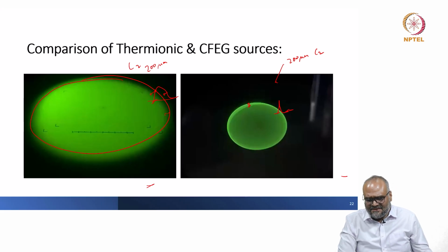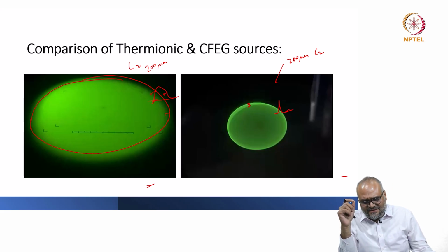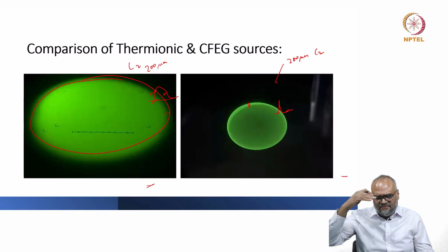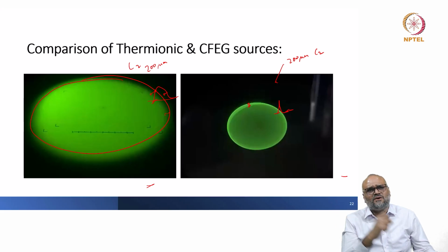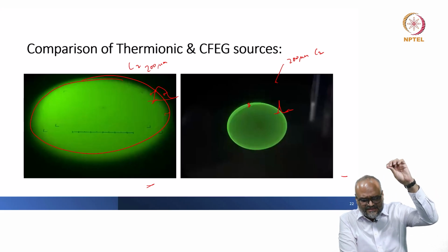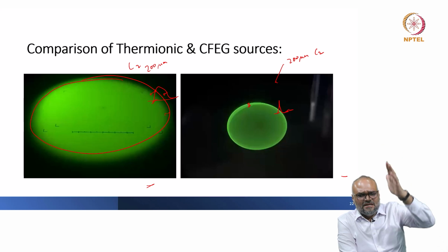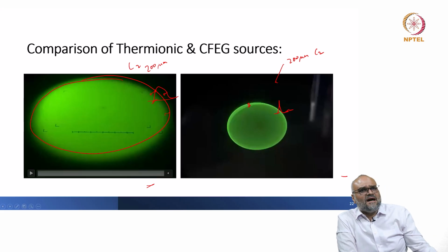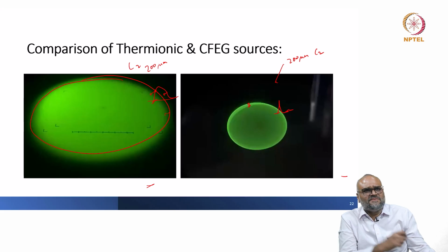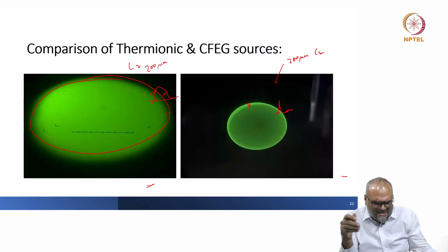Let us have a look at the crossover point that I was talking to you. I am not looking at exactly the specific location at the point before my objective lenses or just at my condenser lenses where the first crossover is, but I am now transmitting the image of the first crossover point through the illumination system of the microscope, and I am projecting the information on the fluorescent screen and seeing how the intensity changes as I am changing the intensity knob or I am converging the beam.